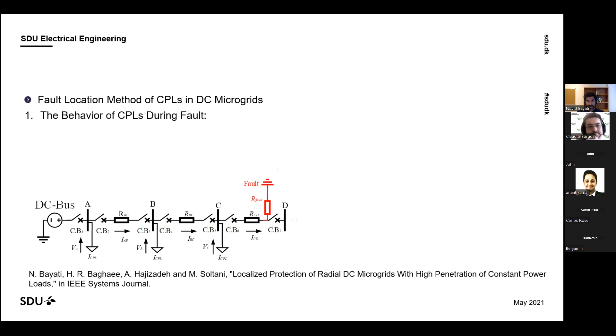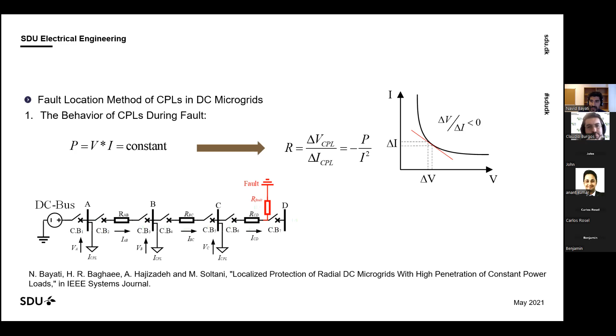So for the load side, we have also some challenges. If we have constant power loads or data centers, the behavior of this load is that the power should always be constant. So if we have a fault, the voltage will drop, and the current will drop as well. When the voltage drops, the current should increase to compensate and keep the power constant. So as we can see here, the delta V to delta I is a minus value. So during the fault, from the constant power loads, we have a resistance whose value is minus, or negative. So the protection is different.